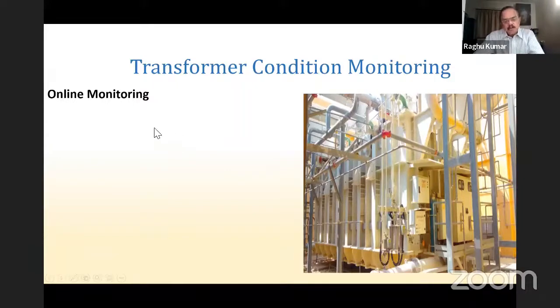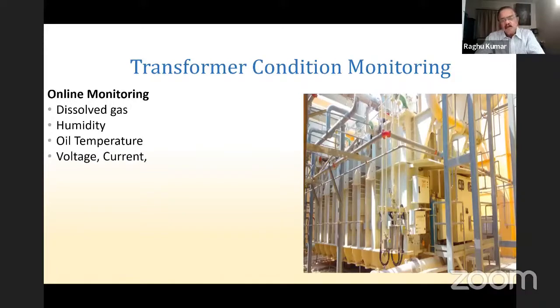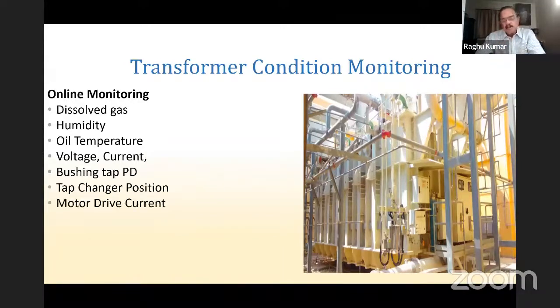And what is being monitored is dissolved gases. There is a decision you have to take whether you want to monitor 1 gas, 3 gases, 5 gases, or 9 gases. In this particular transformer, 9 gases are monitored. Humidity of oil, oil temperature, current and voltage are recorded. Bushing tap PDs are measured continuously. Tap changer positions are recorded. Tap changer motor drive currents are recorded. Fans and pump status are recorded.